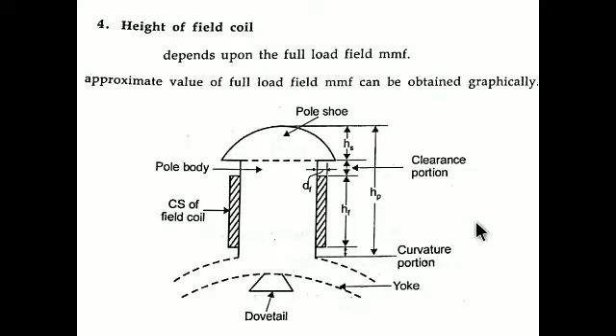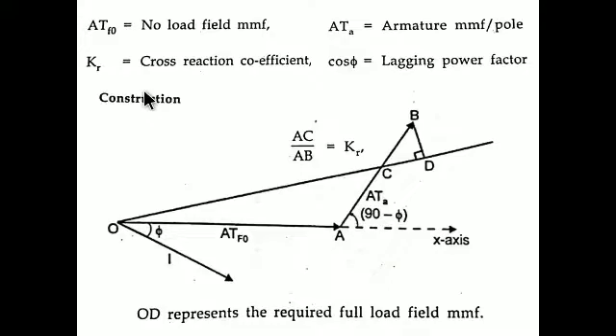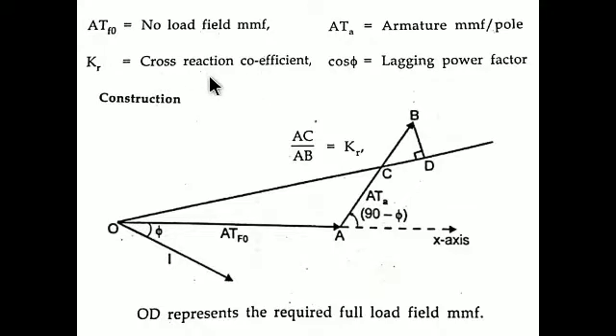To find the full load field MMF, you need four values: ATf0 (no-load field MMF), ATa (armature MMF), kr (cross-reaction coefficient), and cos φ (lagging power factor). ATf0 is found using the standard formula already discussed. ATa is found using the armature MMF formula. The cross-reaction coefficient kr is obtained either from a kr-versus-ψ graph or from open-circuit and short-circuit test curves.